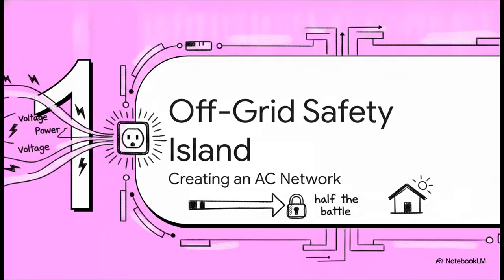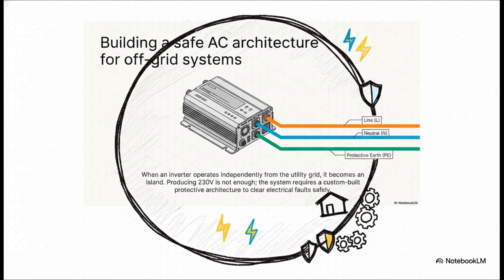Let's get into it. Part 1, the off-grid safety island. Look, we gotta bust a common myth right out of the gate here. Just generating 230 volts of AC power? That isn't enough. When an inverter operates totally independently from the utility grid, it basically creates its own tiny electrical network. It's an island. Now, producing voltage obviously requires your line and neutral terminals, typically your orange and blue wires. But to make that island actually safe, you absolutely have to utilize that third terminal, the green protective earth, to build a custom protective architecture.